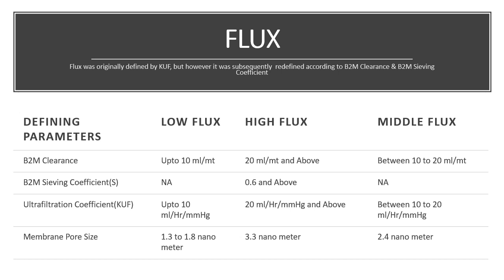High flux dialyzers have a beta-2 microglobulin clearance of 20 ml per minute and above, a beta-2 microglobulin sieving coefficient greater than 0.6, an ultrafiltration coefficient of more than 20 ml/hr/mmHg, and a membrane pore size of 3.3 nanometers.